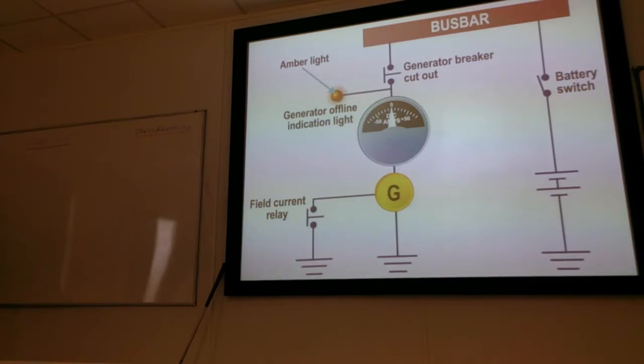So at this point, with a single generator system, if we lose that gen, it stops generating, in case it's an internal fault, we don't want a fire, and it also kicks it off from the bus bar. So now the only thing powering the DC bus is the battery.